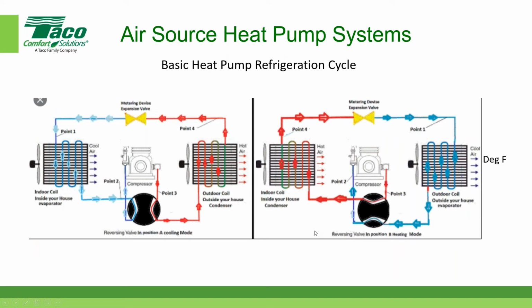So let's look at the unit on the left, it's pretty much the same that I just talked about. Well, no, I'm sorry, the one on the right. It has an indoor coil that's going to heat the space. And there's the compressor. The compressor has a high temperature, high pressure gas leaving, going into the condenser. It's going to give up its heat. In this case, this is an air-to-air heat pump. The one we just showed you, instead of an air-to-air heat exchanger, has an air-to-water heat exchanger. But anyway, that's how it generates its heat. Then it goes through the expansion valve and then through the evaporator, which would be the same as the one we just showed you, an outdoor air-to-refrigerant evaporator. Then it comes back through this valve here into the compressor.